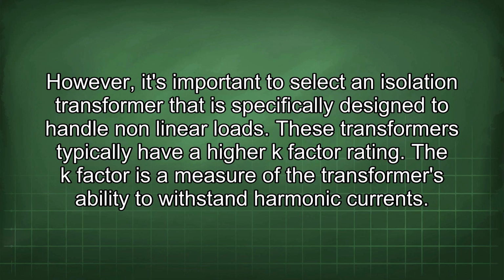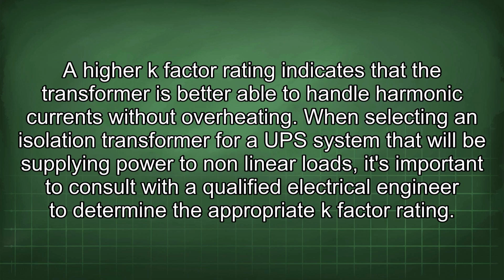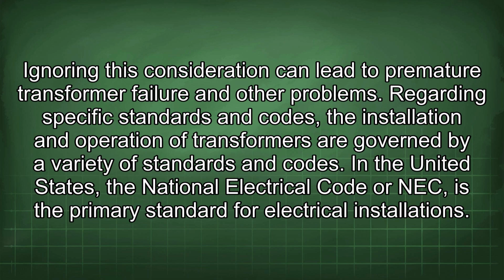However, it's important to select an isolation transformer that is specifically designed to handle nonlinear loads. These transformers typically have a higher K-factor rating. The K-factor is a measure of the transformer's ability to withstand harmonic current. A higher K-factor rating indicates that the transformer is better able to handle harmonic currents without overheating. When selecting an isolation transformer for a UPS system that will be supplying power to nonlinear loads, it's important to consult with a qualified electrical engineer to determine the appropriate K-factor rating. Ignoring this consideration can lead to premature transformer failure and other problems.